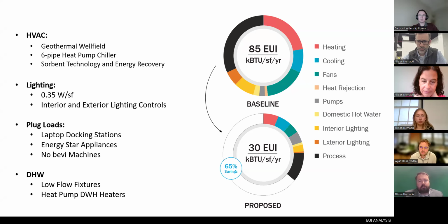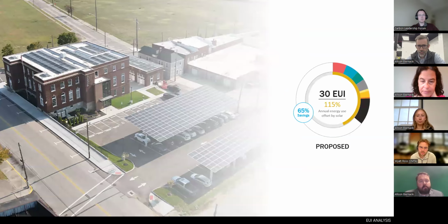If you noticed from the satellite imagery earlier, this building is located right between north and southbound 75, so there's a lot of ozone and PM 2.5, PM1, and PM10 in the ambient air around the building. By reducing how much outside air comes in, we were able to improve indoor air quality well above outdoor air standards. We also did a lot with energy efficient lighting and reduced plug loads.